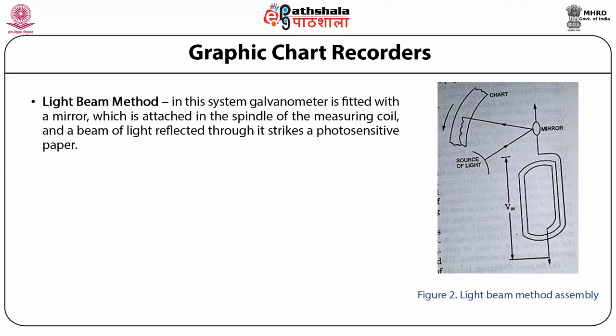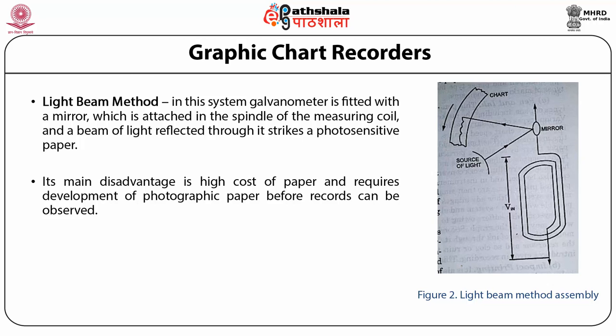E. Light beam method: A galvanometer is fitted with a mirror attached to the spindle of the measuring coil, and a beam of light reflected through it strikes a photo-sensitive paper. This method works well at higher frequencies and allows relatively higher chart speeds without compromising resolution. Its main disadvantage is the high cost of paper and the requirement to develop the photographic paper before records can be observed. This method is not suited for real-time monitoring.